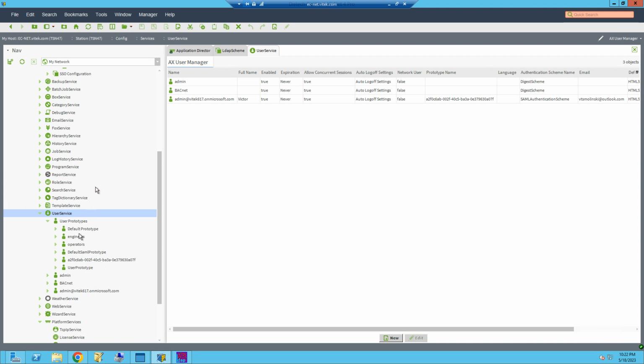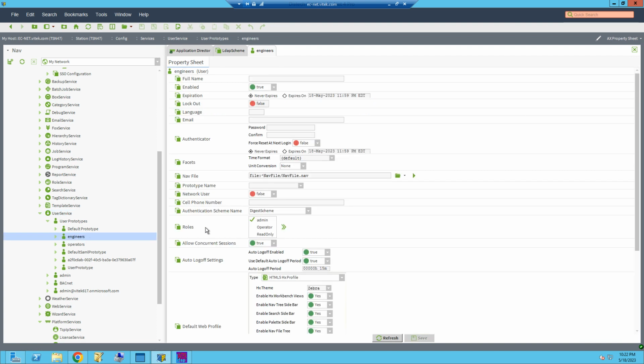Now we know how to do that using the roles and the category service. So what we really need is a way to associate the roles and categories in the Niagara station to a certain group membership that these users are going to have when they get cached in Niagara once they authenticate, right? So this setup here tells me that LDAP should have users that are going to be members of the engineers group and members of the operators group.